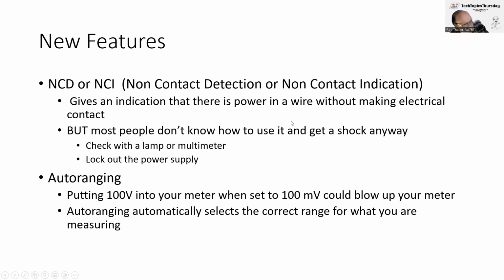This feature is designed to let you know if there's power in a wire without making actual electrical contact. Most people don't know how to use this, and it depends how you hold the meter whether it works or not. Before using it, test it on a known wire to make sure it's actually working, because people end up shocking themselves thinking there's no power when it just doesn't indicate anything.